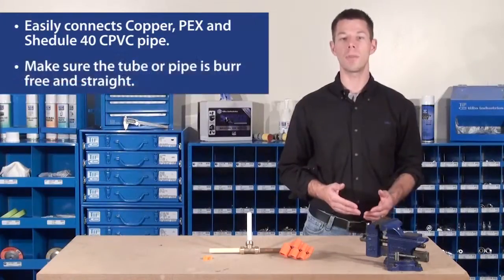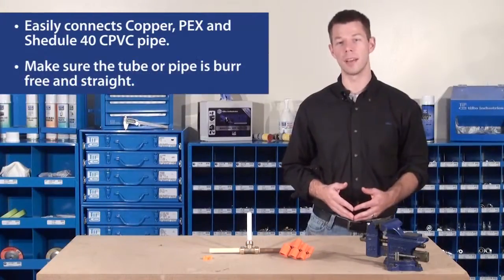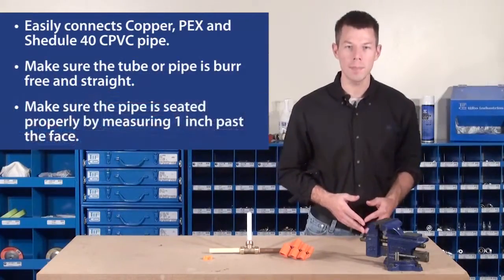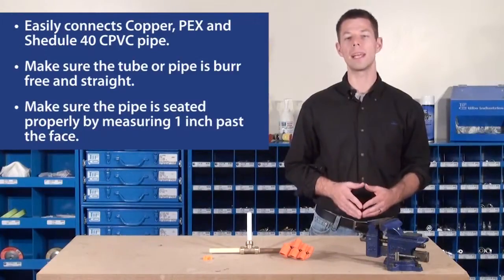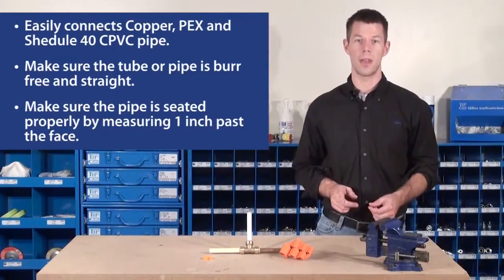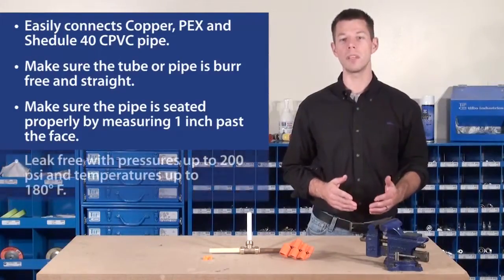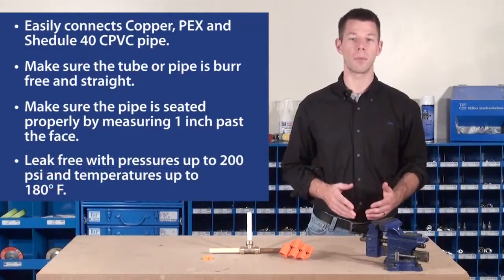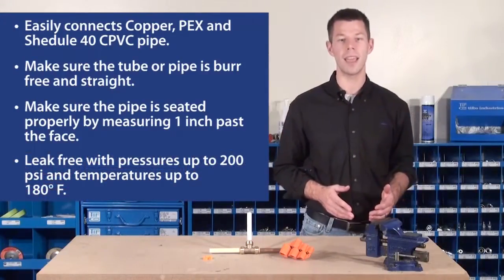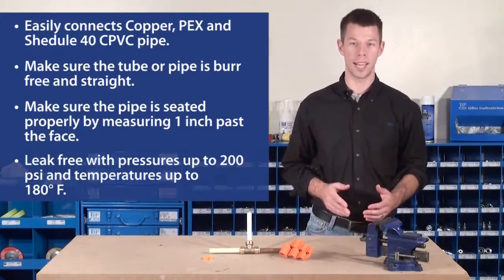Make sure the tube or pipe is burr-free and straight. Also, make sure the pipe is being seated properly by making a mark 1 inch past the face. After you hear the click, the assembly is secure and leak-free for pressures up to 200 PSI and temperatures up to 180 degrees.